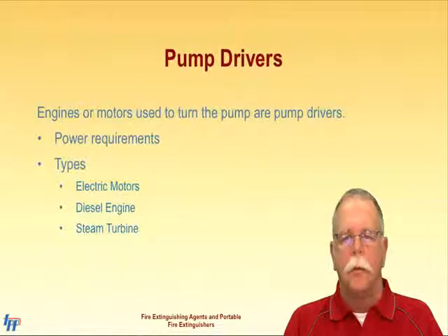The driver is the mechanism that turns the pump. The pump is required to turn at a certain speed to produce a predetermined flow and pressure. Therefore, the driver must be of sufficient power to turn the pump accordingly. Electric and diesel engine drivers are definitely the most common drivers today. Gasoline engines are no longer allowed due to the lack of reliability caused by the ignition systems.